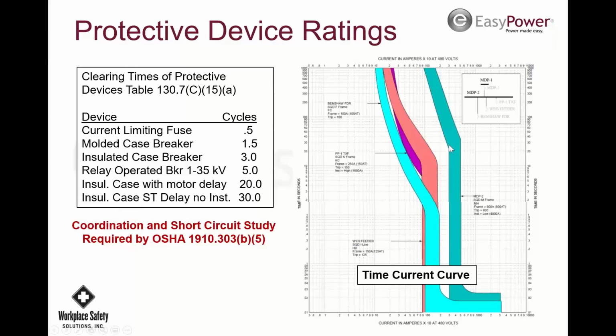So that's what this is. So this breaker feeds the main distribution panel. Then there's a breaker in that panel that feeds a 480 volt panel, and that's a main breaker for that panel. And then this is a breaker in the panel that feeds a motor. The motor goes bad and is overloaded for whatever reason, and so it trips the breaker as it's supposed to, because that's the closest one to it, time-wise. Then if that doesn't trip for whatever reason, then you've got the main breaker. And so this is all coordinated. And that's good for 20 or 30 seconds. That's how much it would take for that particular overload to occur. So if you have a 50 amp breaker and you're drawing 55 amps, it may take 20 or 30 seconds to trip. But the right breaker is going to trip.